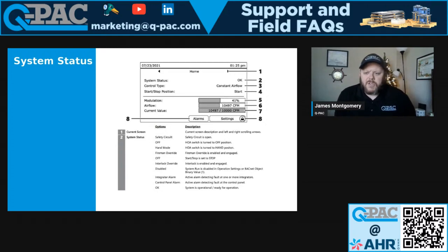And then the current value, this is a pretty interesting setting that our developers put in. When this thing's chasing or following a PID loop or a set point, you'll see a red and a green bar. So essentially target and how close it is to getting there. It's kind of filling up that bar there. It's pretty interesting. There's a little more stuff that you can see on here. You notice there's a date and a time. Those can be verified and set. I'll talk a little bit about that if anybody's interested in how to get to those settings.